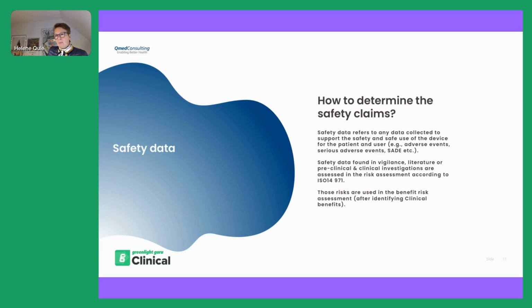Safety claims, or safety objectives, are identified through, for example, the vigilance databases that we have available, so the MAUDE database and the TPLC under the FDA, from the literature, or from our own preclinical and clinical investigations. The risks are assessed through the risk assessment according to the standard that we just mentioned, ISO 14971. And remember to use the most recent version. We often see that the old version is used in the risk assessment.